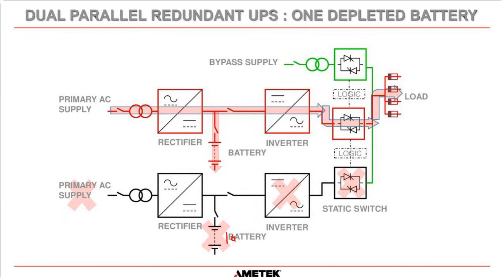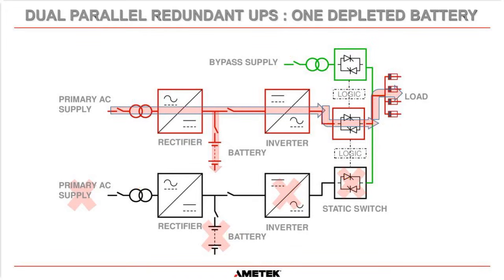Then if this battery gets down to that 105 volt level, we tell this static switch to turn off. We trip this breaker here, and the inverter will turn off. Rather than transfer to bypass on this UPS, and I'll explain later why we can't do that, we turn this UPS off. So this is no longer supplying that 5 kVA. Now UPS A will supply the full 10 kVA to the load circuits. Bypass is still there if needed, but UPS A is taking care of the full load. And this will all be done without any disruption to your load circuits whatsoever. Obviously, you will get some alarms on UPS B, but UPS A will carry on going regardless.